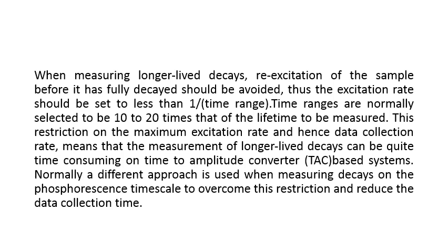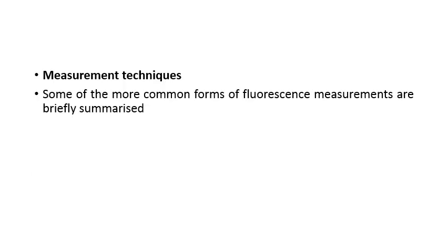This restriction on the maximum excitation rate, and hence data collection rate, means the measurement of long-lived decays can be quite time consuming for a time-to-amplitude converter based system. Normally, a different approach is used when measuring decays on the phosphorescence time scale to overcome this restriction and reduce the data collection time. We have discussed time resolved measurements.